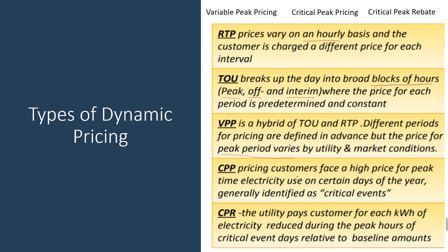The fourth type is critical peak pricing, where customers face a high price for peak-time electricity use on certain critical event days — for example, in India, consumers pay higher charges during Diwali or New Year periods when demand is high. The fifth type is critical peak rebate, which is the opposite: the utility provides an incentive to consumers if they save electricity during a critical event. The utility pays the consumer for each kilowatt-hour reduced — for instance, if their baseline is 10 kWh and they consume only 5 kWh, they receive an incentive for the reduced 5 kWh.